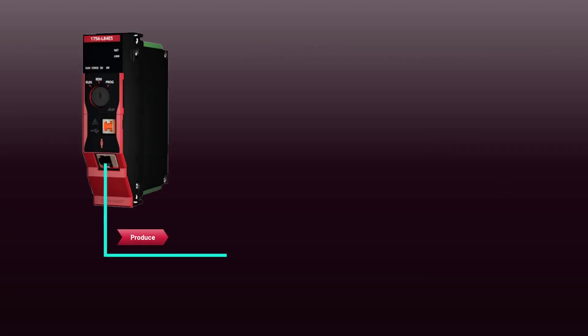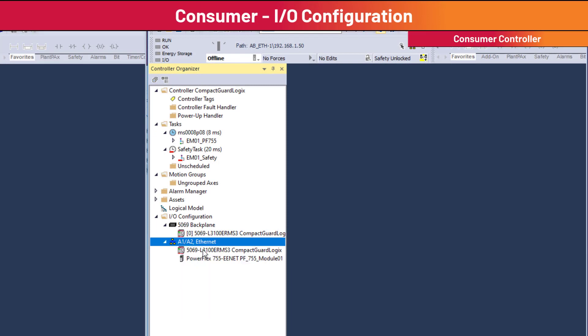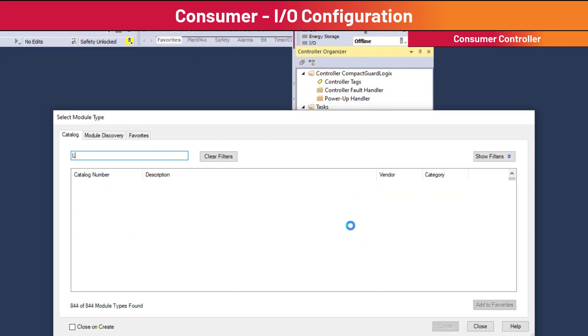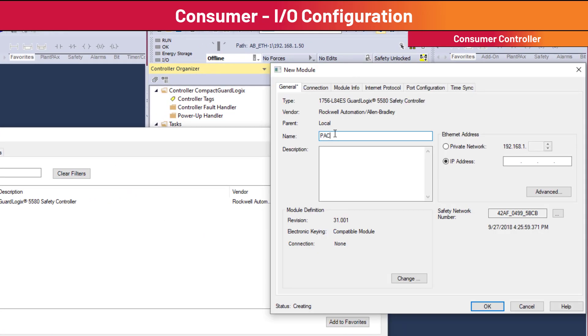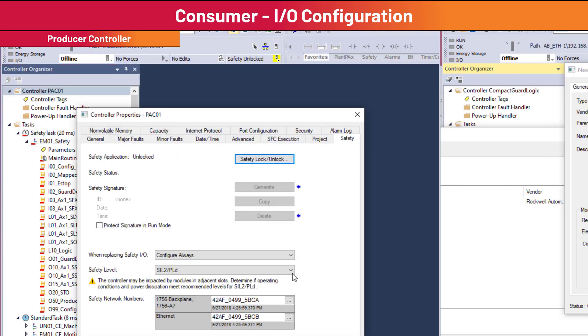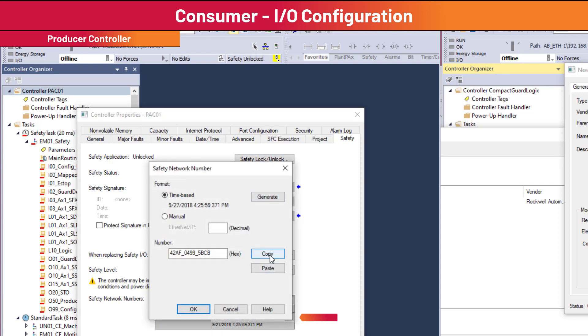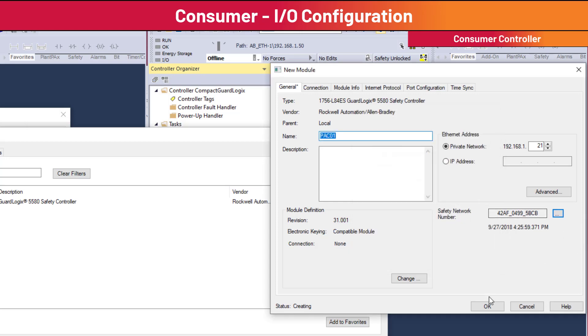The configuration for the producing controller is now complete. Now let's configure the consuming safety connection. Add the producing controller to the IO configuration of the consuming controller — you must know the producer's catalog number. Provide a name for the producer, IP address, and safety network number. The producer safety network number is found in the producer controller properties under the Safety tab. The 1756-L84ES has two safety network numbers: the first is for backplane communication and the second is for the front Ethernet port. Since our project is communicating out the front Ethernet port, the second safety network number is copied and pasted into the new module properties of the consuming project.